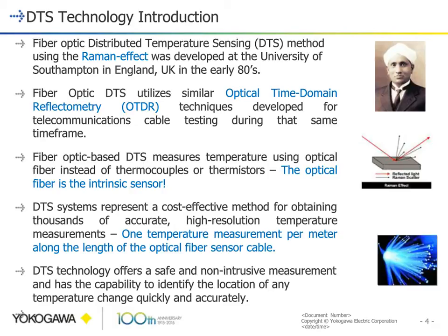But the University of Southampton was very instrumental in the development of early specialty fibers, and especially using fiber to sense physical measurements. The technique that we've deployed with our solutions, we're using a Raman technique. This was discovered, as you might guess, by a Dr. Raman, and what he learned was that when you pulse the laser down a fiber, part of the reflected signature that comes back to you provides some temperature information, so that in effect the optical fiber becomes an intrinsic sensor.